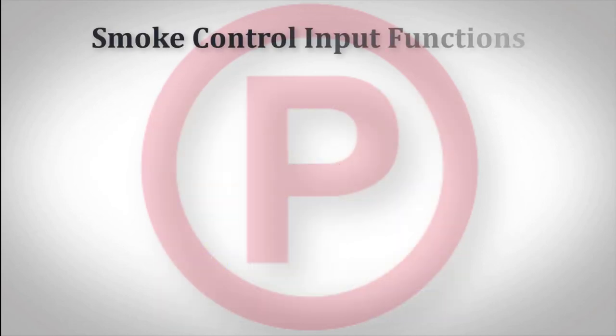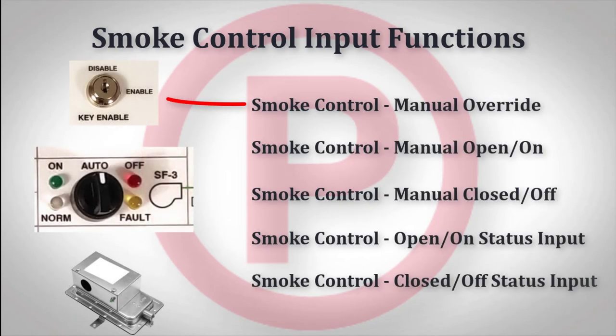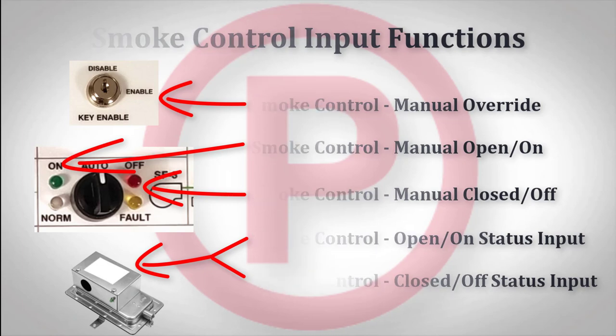To accommodate standard smoke control systems, the Potter programming software has several point types specifically for smoke control. The following inputs are available: smoke control manual override for the key switch enable on the firefighter's smoke control station; smoke control manual open, on, and closed off to monitor the position of the manual control switch; and smoke control open or on and closed off status inputs to monitor the positive feedback contacts of the fan or damper.